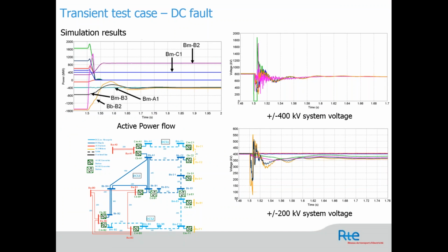Usually in a converter station, they include a surge arrestor, which should limit this overvoltage shown here. In the DC grid benchmark, we did not include the surge arrestor, which is why you have such a huge overvoltage. If you have a surge arrestor, it will cut off this overvoltage. But of course it's still an issue that should be dealt with, and this is one kind of issue that should be addressed in DC systems. So here, what we are providing is a benchmark to see what issues can occur and how to deal with them.